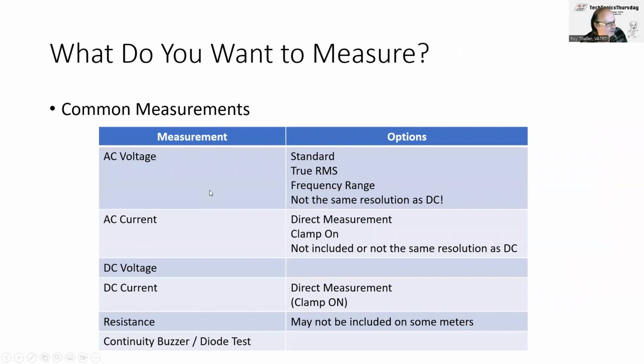When you're looking at AC voltage, this seems to be quite standard, although some meters may not have AC, and some meters may not have the resolution. As for DC, you might be able to measure like 100 millivolts, but for AC it might only start at 10 volts or 100 volts. One of the things you want to look at is whether it's true RMS or not - if you're measuring other than a sine wave, like a square wave or a triangle wave, are you going to get a true reading or not? And you're going to pay for all of these features.